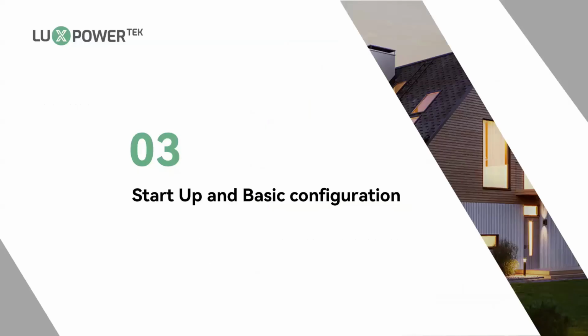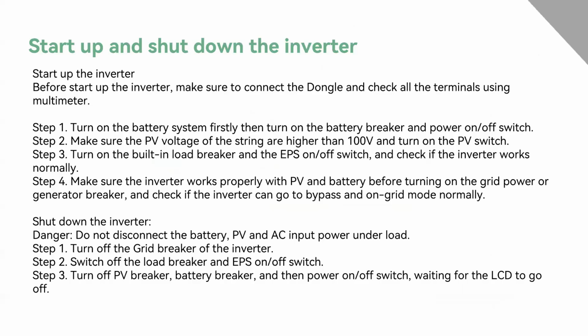Okay, that's all for the installation and wiring. When we have finished the installation, we need to turn on the battery and the whole system, for example the battery and the inverters, to check if it's running normally, and do some basic settings like grid type and the battery brand on our inverters. So firstly we have to start up the inverters, and afterwards we need to shut down. So there are the startup and shutdown procedures.